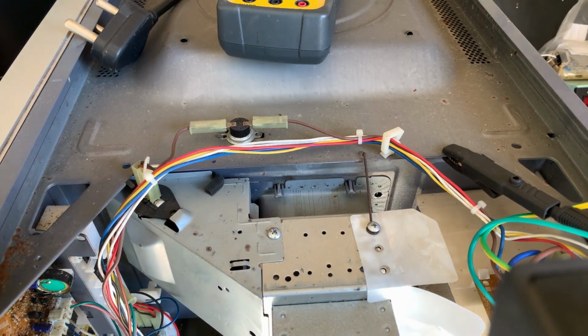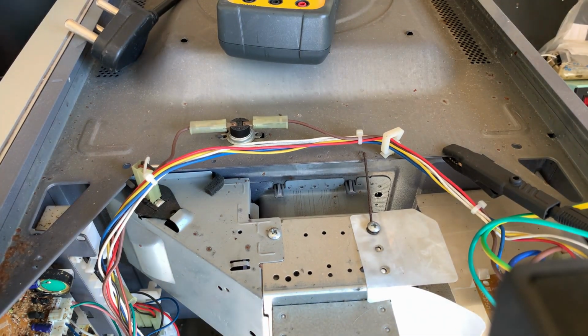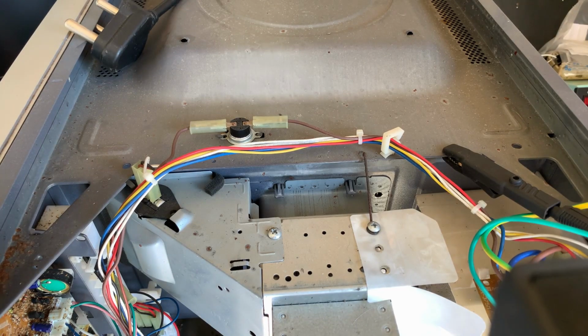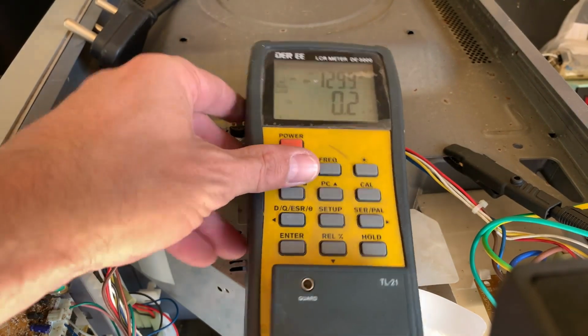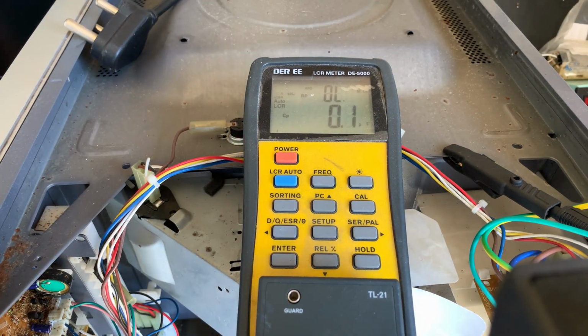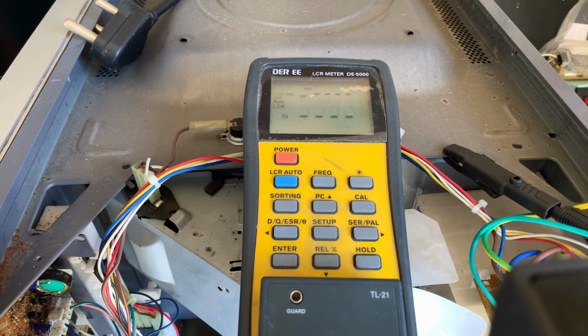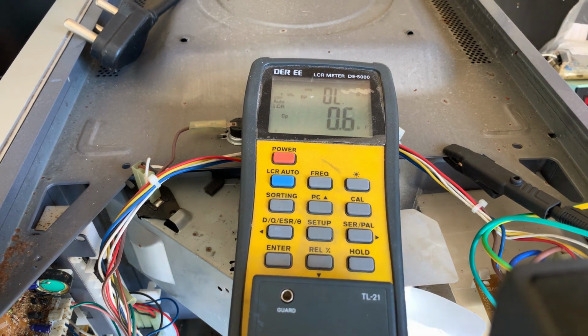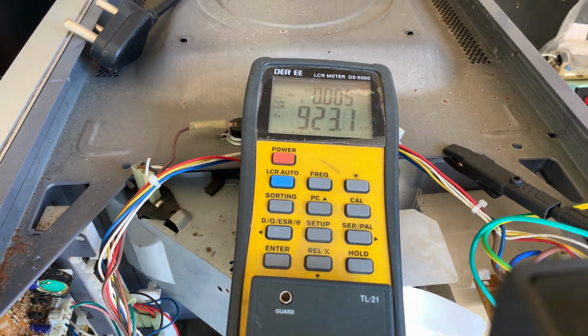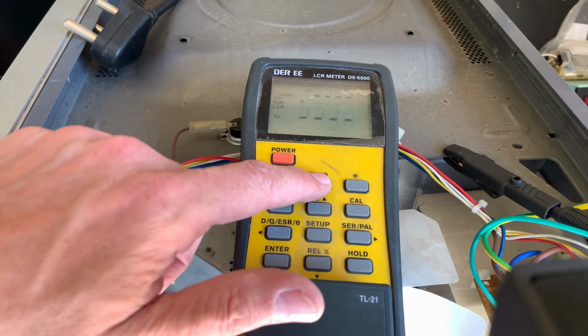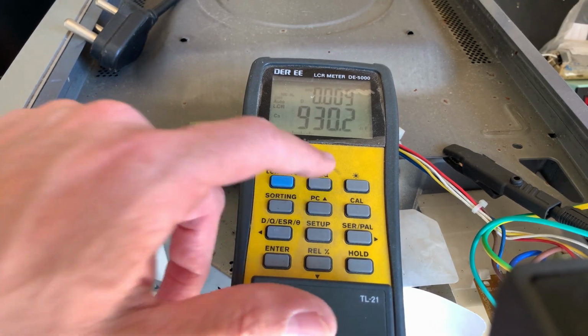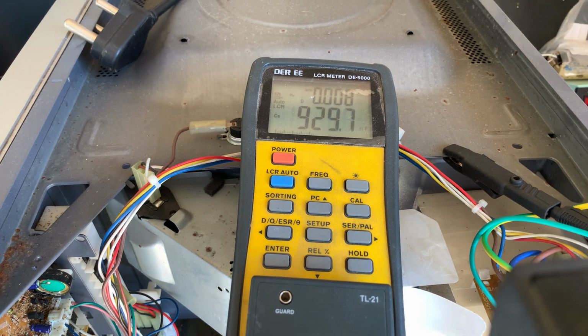So what I'm going to do, I'm just going to move my multimeter out of the shot, and what we will do is put in place our LCR meter. And why you want to do this is because I can set the frequency of the LCR meter. So I'm just going to clip it on, and we're going to set it to a frequency of, surprise surprise, 120 Hertz. Why 120? Well, in the States your line frequency is 60 Hertz. You rectify that, you will have 120 Hertz.